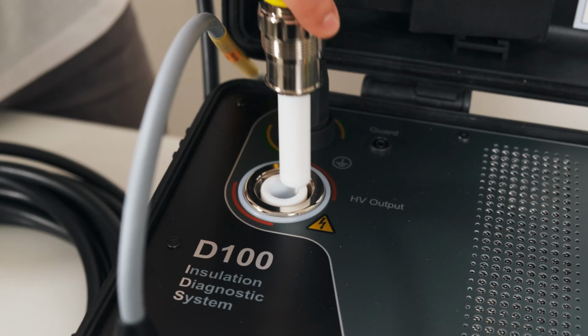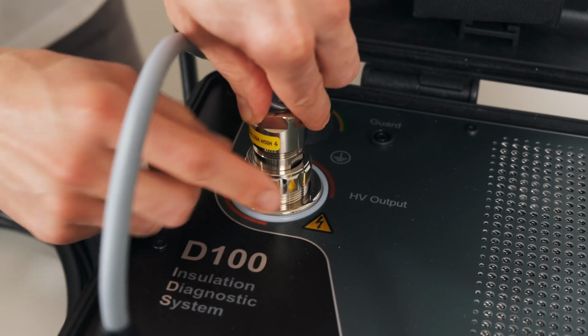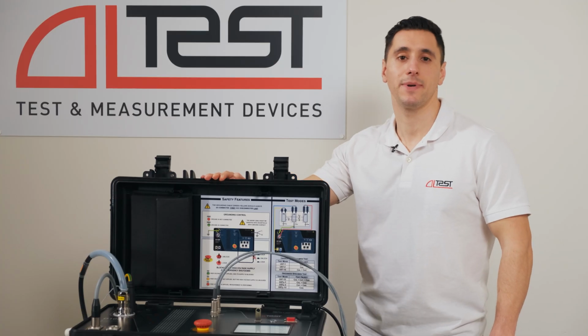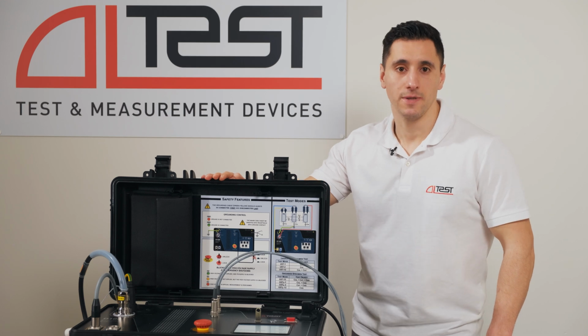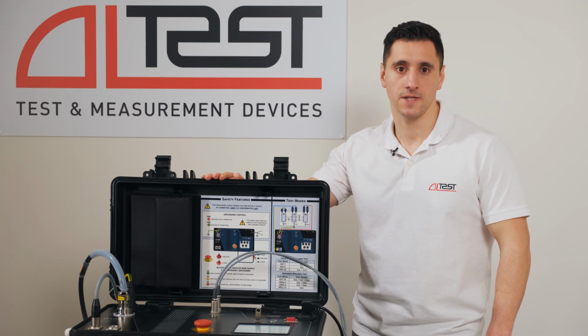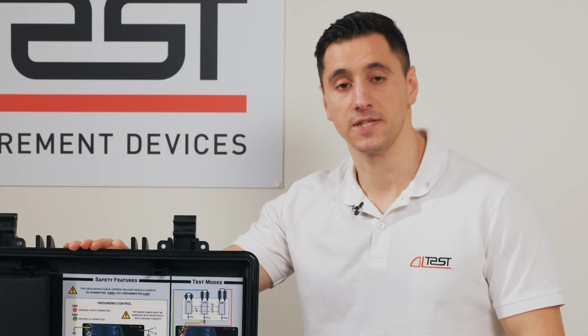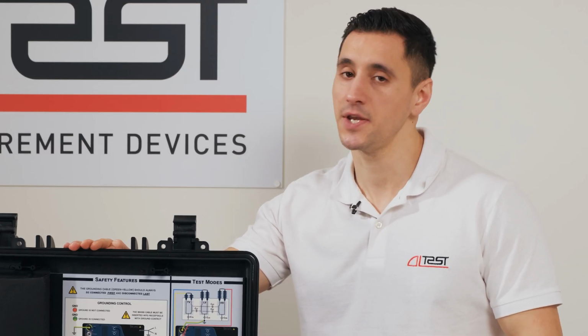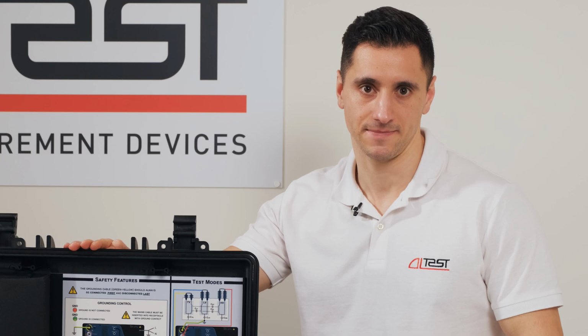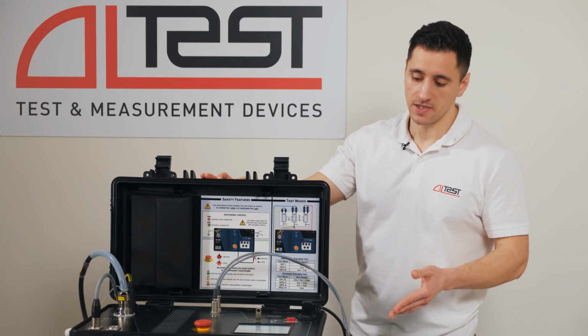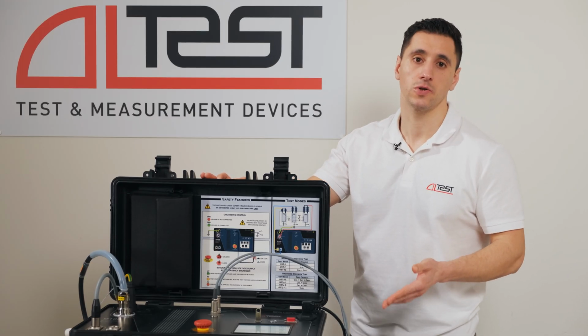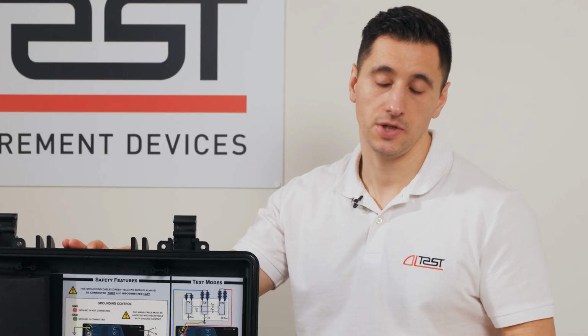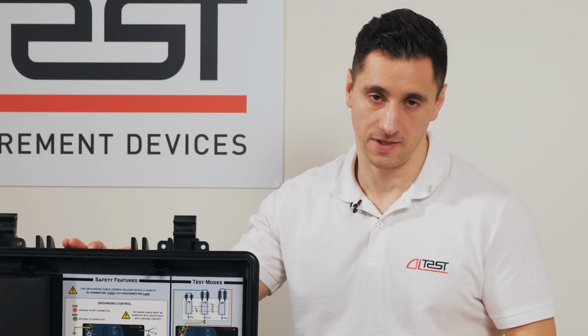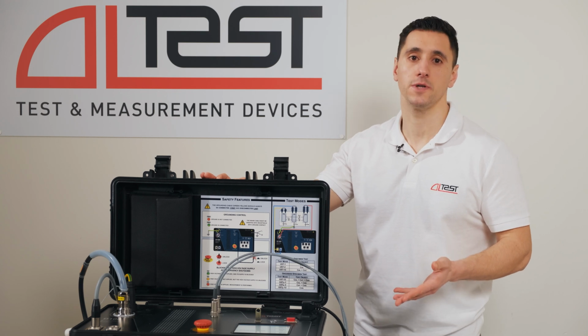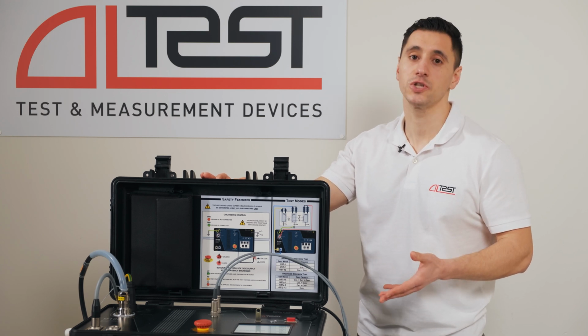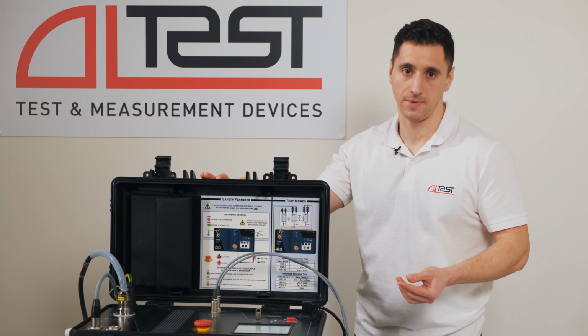Connect the high-voltage cable to the appropriate socket on the front panel of the device. The design of the device provides that voltage is present only at the end of the high-voltage cable. All available current carrying parts are not under high voltage. D100 operates on AC power with a rated voltage from 100 to 240 volts and a frequency of 50 or 60 Hz. The outlet that powers D100 must have a protective grounding contact.